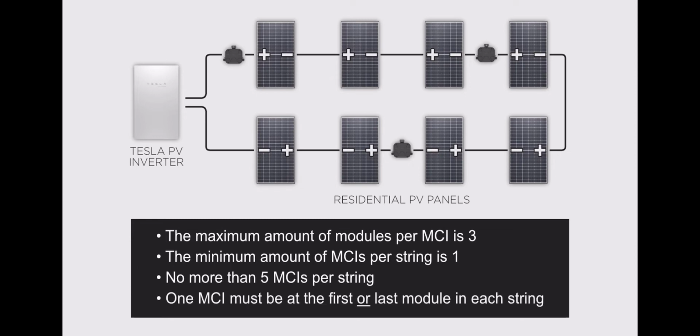Finally, always connect an MCI to either the first or the last module in each string. For example, you should have one installed at this end or the other end.